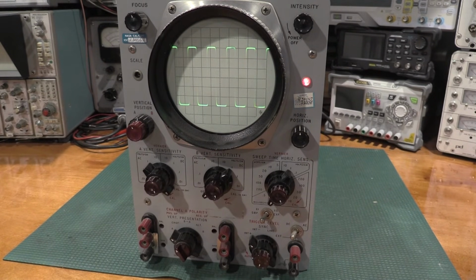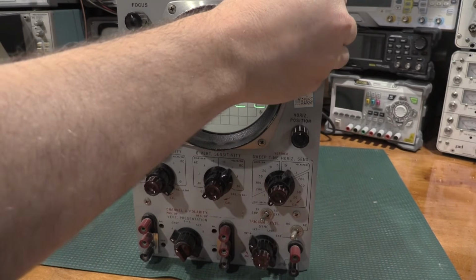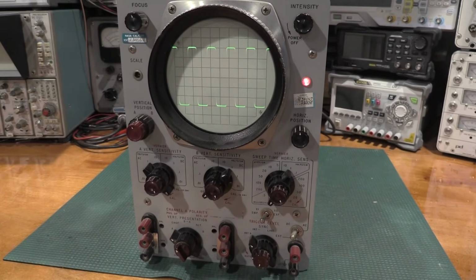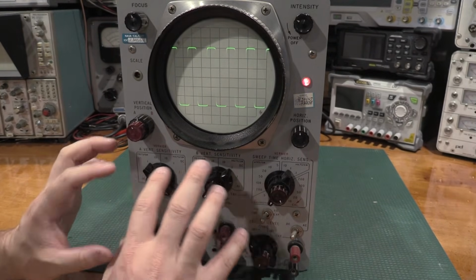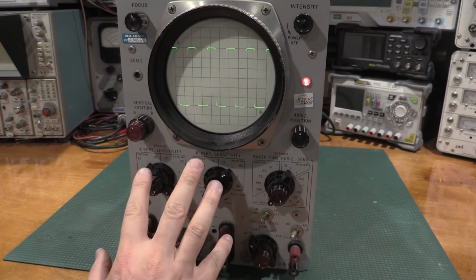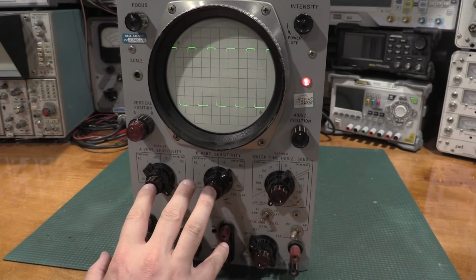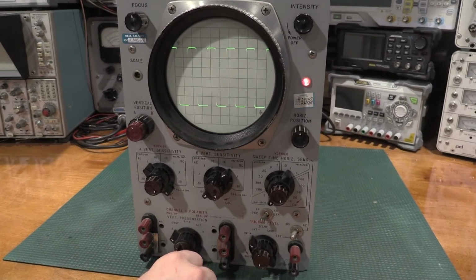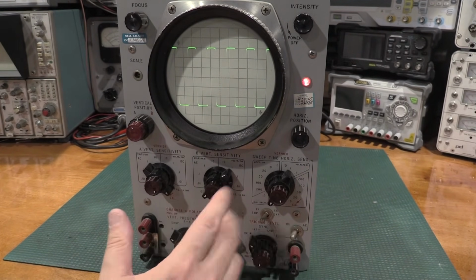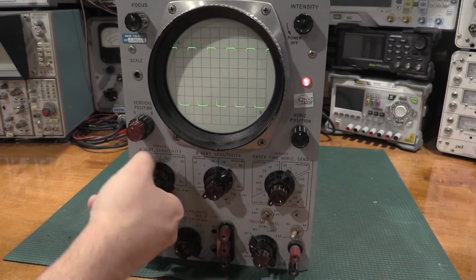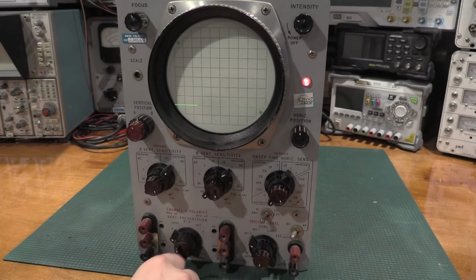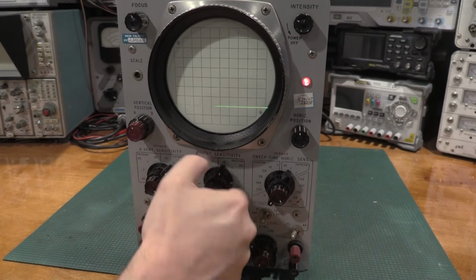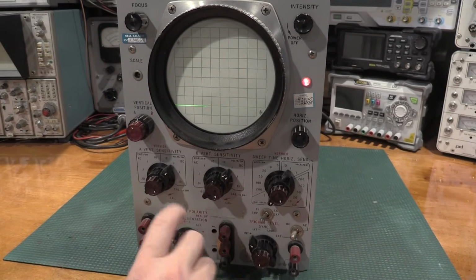All right, so let's put this in. Let's hook up my calibrator. I've had it warming up. And we've done a quick calibration with the internal calibrator of the scope. Let's check and see how accurate that is in the vertical, if it's still accurate or if it's way off. So we're going to go to 1 volt per division DC coupled. On this scope, that is that position.